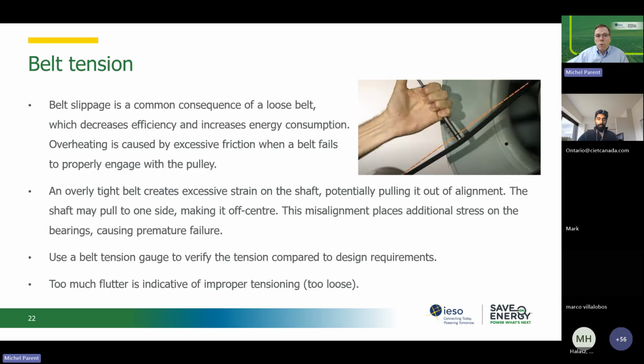Obviously, again, we do have a slide about PM where it has to be realistic. If you've got too many tasks in your PM program, it's a waste because people cannot get to all of the tasks in your PM program. But belt tensioning for the larger system should be verified. So you put that little tensioning tool there, and depending on the deflection, it will tell you if the belt has proper tension. And like I said, if there's a lot of flutter in the belt, which I see often, it's because of improper belt tensioning.